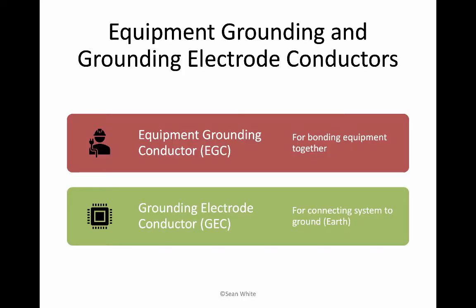And here are our EGCs and our GECs. The equipment grounding conductor, the EGC, is for bonding the equipment together, so connecting it all together. And then the grounding electrode conductor is for connecting the system to ground, to earth, to the electrode. The grounding electrode conductor is not as common as the equipment grounding conductor. For most grid-tied PV systems, we are not doing grounding electrode conductors. It used to be that we had to do that, and it was kind of a pain. Fortunately, we don't have to do that too often anymore. That was the DC GEC, and we used to have to go over that over and over again. But now the National Electrical Code doesn't require us to do that, and we are going to talk more about that when they lay it out in 690.